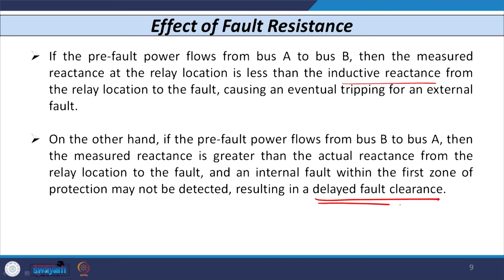So, as I told you, because of the power flow, if it is from A to B, then the relay will show a value of that part that reduces. So, the measured impedance is only this, which is within the zone of the circle. If I draw the circle from here, this is your B and this is your A, then this point comes inside the circle. So, even though the fault is somewhere here, the relay may overreach. And it may be possible that in this case the relay underreaches, because the fault is within the zone of the relay, but the relay will measure this value because of the increase of this factor 3 RF IF by IA. So, the relay will measure a higher impedance which is greater than the set value.